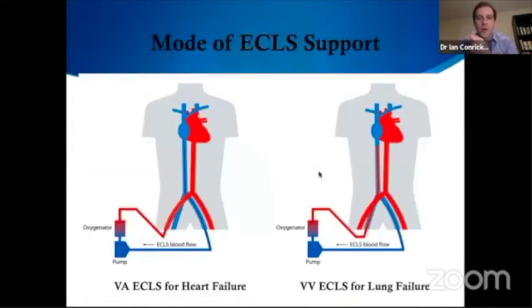The two broad modes of ECMO support or ECLS support, and I hope this projects reasonably well. You can see drainage flow from the venous side of the system and return flow to the arterial side of the system. Again, VA ECMO for heart failure. On the other side, you have drainage from the venous side of the system and also return to the venous side of the system. So oxygenated blood is being delivered back to the venous side, providing just lung support, just gas exchange, no mechanical support, for VV ECMO.